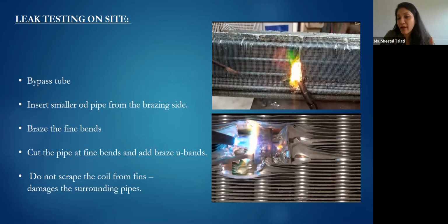First thing, you have to check which pipe is leaking. Add nitrogen and dip it in a water tank or check it with a soap solution. Bypass that pipe. It's in a hairpin shape, so you will have to bypass 2 tubes if one pipe is leaking and make a fresh circuit.